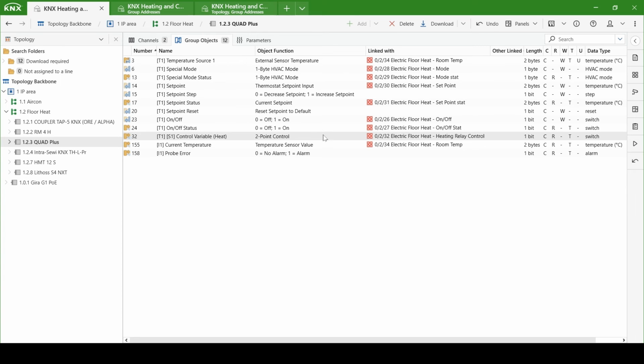Now take big note here, this is what I'm talking about. This is the actual input of the temperature probe, and that's the temperature source for the thermostat logic. They're both in the same group address. I know it sounds funny, but in this case the KNX device sees them as two different parts of the device, so you have to link them. Don't automatically assume they're already linked.